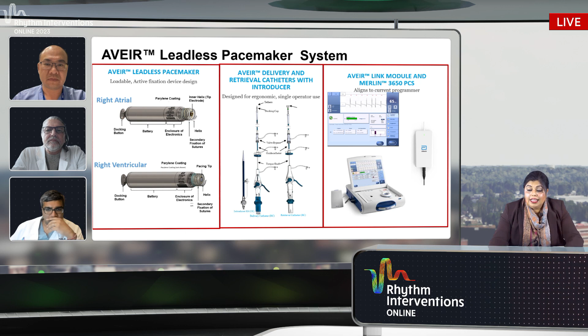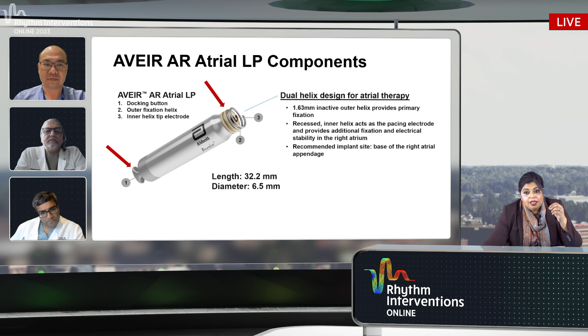Now, looking at the device as such, the atrial device, or the atrial leadless pacer, has three components. You can see the main components as such are the docking button, which allows for not only delivery but also retrieval of the system. The helix fixation, there are two helixes there. So the outer helix, which is the electrically inactive helix, provides the main or primary fixation.